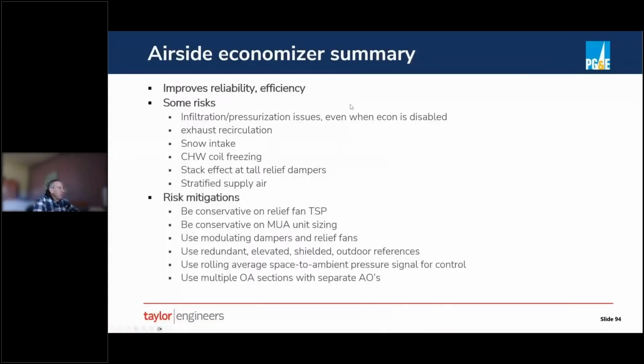Summarizing air economizers, they generally improve reliability and certainly improve energy efficiency. An air economizer is pretty much the most efficient way to cool a data center, even compared to liquid cooling, I would argue. But there are risks. There's a risk of infiltration and pressurization issues. I talked about the data center that we worked on that had a lot of dust that was literally causing equipment failures. And those issues can persist even when the economizer is disabled. Because you have such large outside air and exhaust air dampers, it's hard to keep the data center even tightly sealed when the economizer is disabled. So maintaining pressurization is sort of the solution there. Even when the economizer is disabled, sometimes you'll need to have a means of pressurizing the data center.